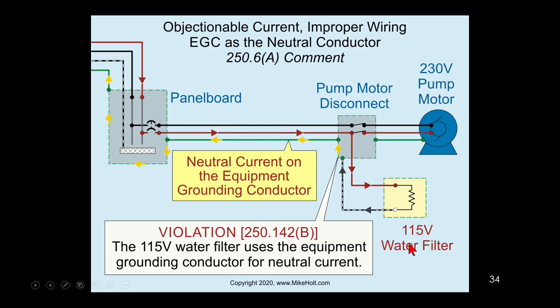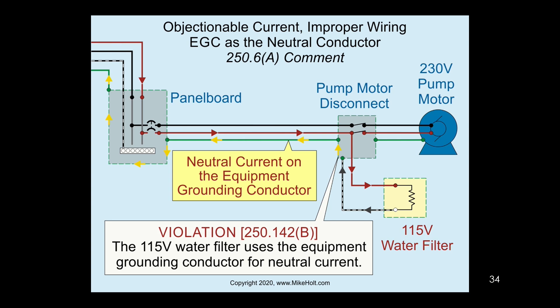Here is a 230-volt pump motor and somebody wants to add a 115-volt filter. They ran two hots and an equipment grounding conductor out to the motor disconnect, or maybe even putting in a receptacle. Somebody wants to put a receptacle out there — they've got two hots and an equipment grounding conductor, so they connect one hot and use the equipment grounding conductor as a neutral, letting electrons travel back to the source. That means you're using that equipment grounding conductor to carry neutral current.